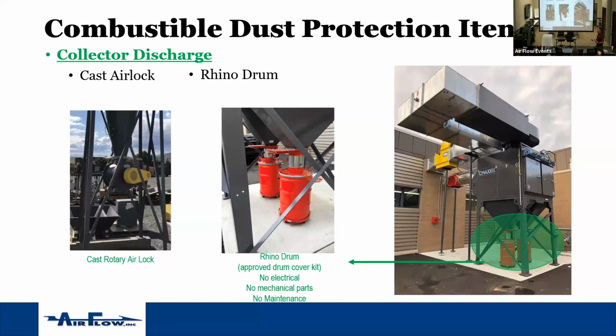The Rhino Drum is completely the opposite. This is a wide open, free flowing chute straight down. No maintenance, no moving parts, no electrical, no controls. The key is you have to keep these drums with it. These are not a standard 55-gallon drum. They're a thicker drum. They're actually tested to hold back the pressure of an explosion itself with this coupling device on it. When you go to change these, there's a slide gate that you can close. So you can continue to run, your dust collector can continue to operate. You can close your slide gate, change your drum out, dump it, come back, put it right back online.